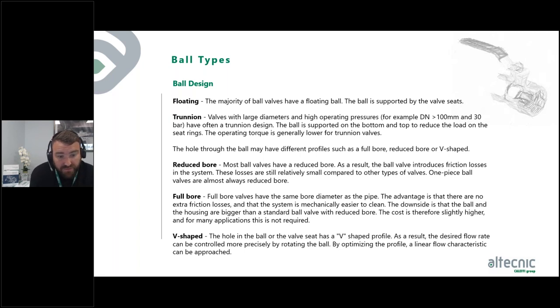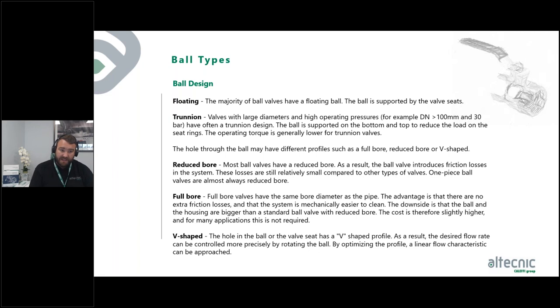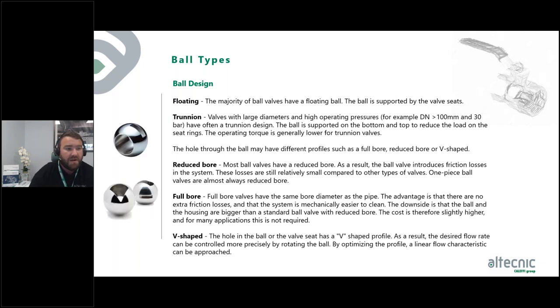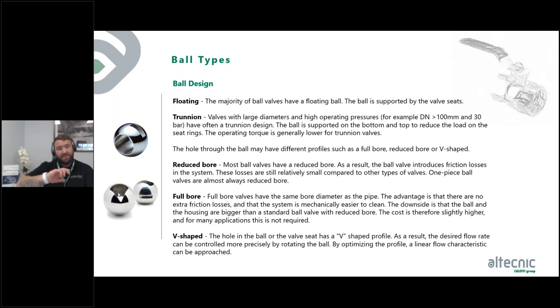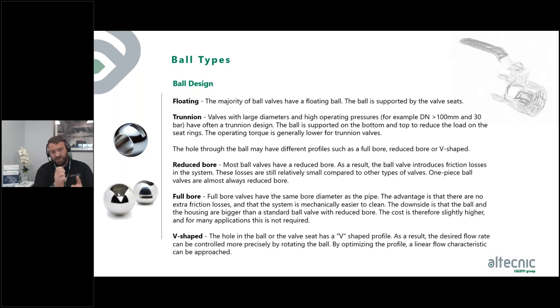A V-shaped ball has a V-shaped profile in the ball and valve seat. As a result, the desired flow rate can be controlled more precisely by rotating the ball, and by optimizing the profile a linear flow characteristic can be approached. We start to see these V-shaped balls as we move toward light commercial and commercial installations. As the valve rotates on its axis and the V opens up, we get a different flow rate because we've moved away from a central bore — I call them characterized balls because each has its own flow characteristic.